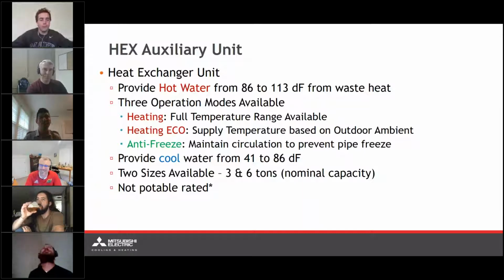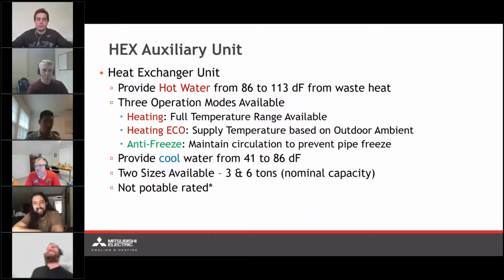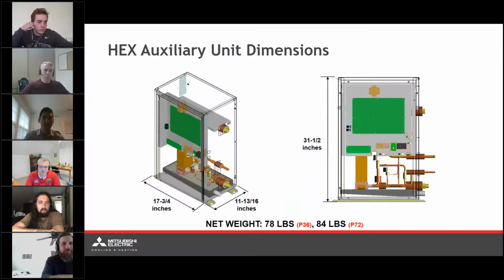So, the aux unit is going to be in 3 and 6 tons of nominal capacity. Just to reiterate, these units aren't potable rated, closed loop systems only. They're not going to be able to provide the potable water just with themselves. And just to give an idea of the size of the equipment, here is a dimensional diagram. Again, it's going to be 1 foot wide, 18 inches deep, and 31 inches tall. For the aux unit, this is going to be around 80 pounds, as opposed to the booster unit. That's going to be adding a little bit more because of the additional compressor.